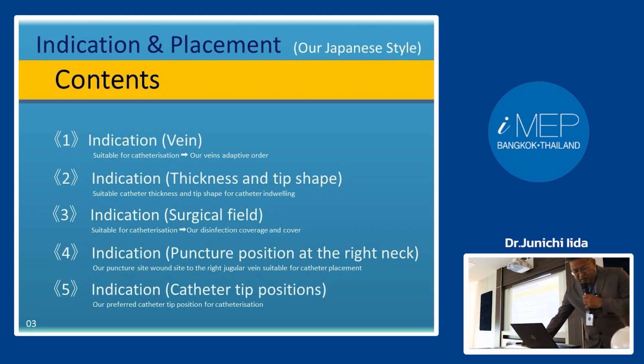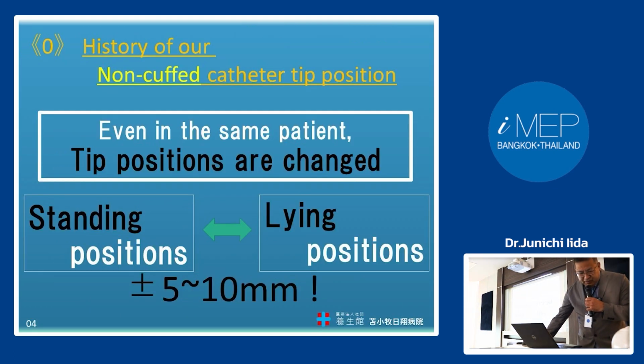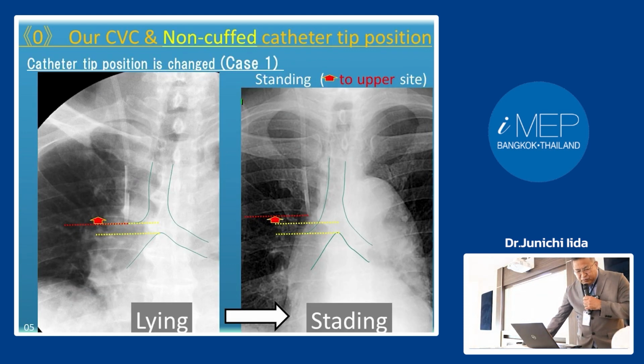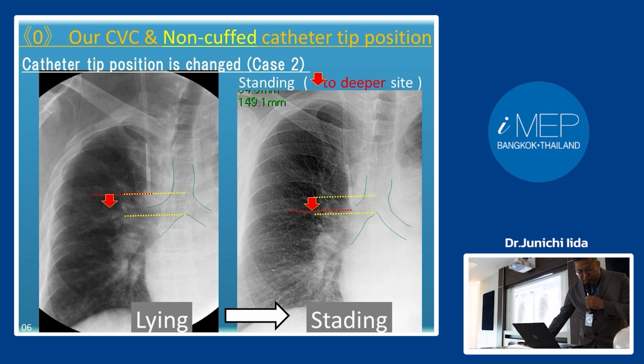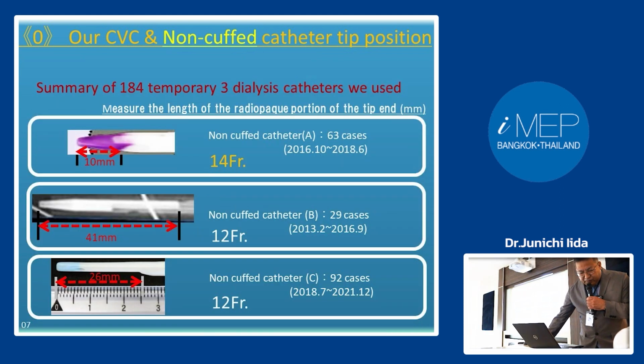Our indication and placement for cuffed and non-cuffed catheters. 5 indications for catheterization. Even in the same patient, catheter tip positions change by 5 to 10 millimeters between standing and lying. In the standing position, in case 1 the tip position changed to upper, but in case 2 the tip position changed to deeper.